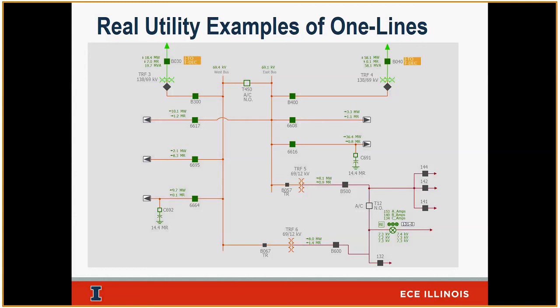This is what a SCADA one line would look like. This will be the last thing I'll talk about. A SCADA one line is actually what an operator in a room sees. SCADA, again, is supervisory control and data acquisition, so I have that information available to me in real time. As an operator sits here, he sees a 138 kV line coming through, and there's a transformer that steps down the voltage to 69. That diamond is the symbol for an LTC in my utility. So that transformer has a load tap changer, controlling the voltage right there.